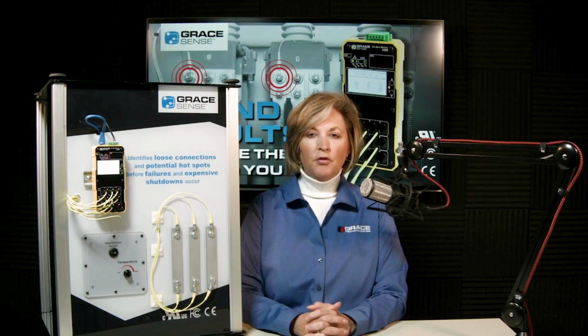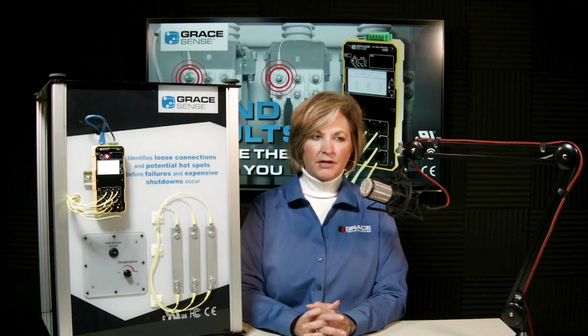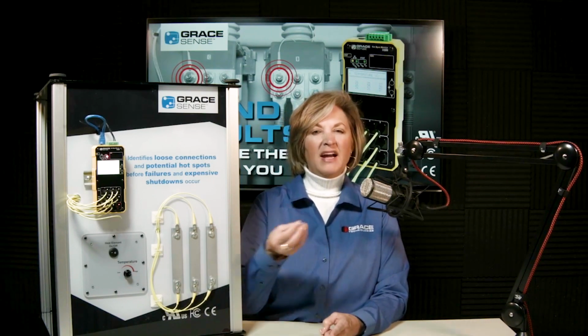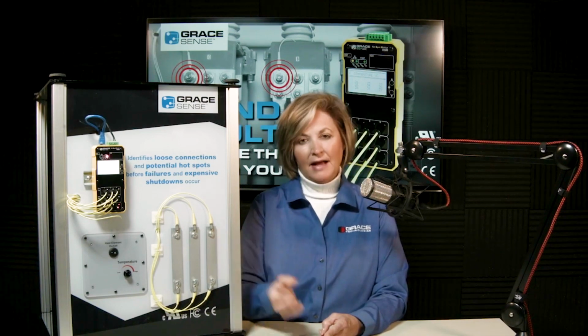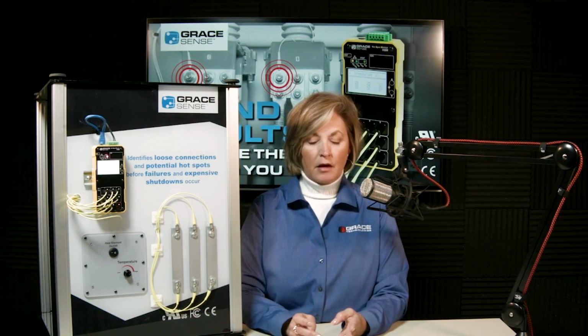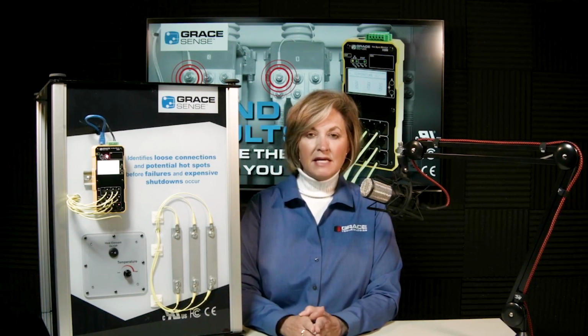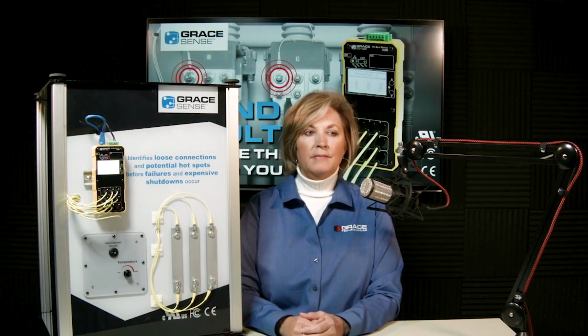So for medium voltage switchgear, for example, we have determined that there are several points which we consider a potential failure point. And that would be the field terminations, right? The cable terminations, where you're already thermal scanning if you have that program going. So cable terminations, the line and load sides of your breaker, even if it's on the run back, it's okay. PT rollout compartments, maybe your main bus entrance or your main breaker entrance and your main bus in the equipment. Transformers, for example, on the secondary side of your transformers. Medium voltage switch MCC, perhaps on the T leads and main bus. Contactors, any moving components, any moving locations.